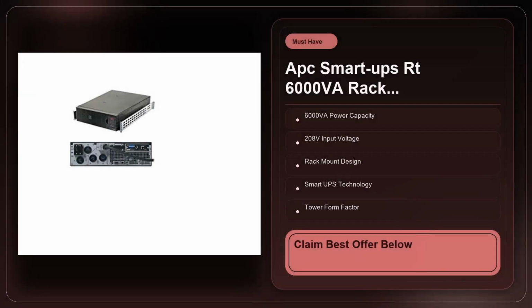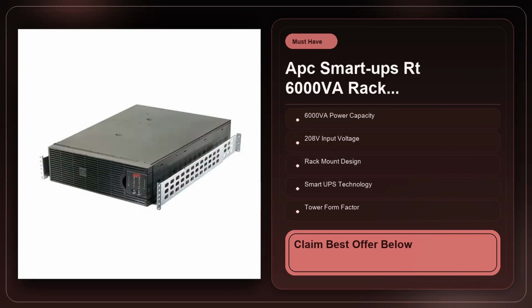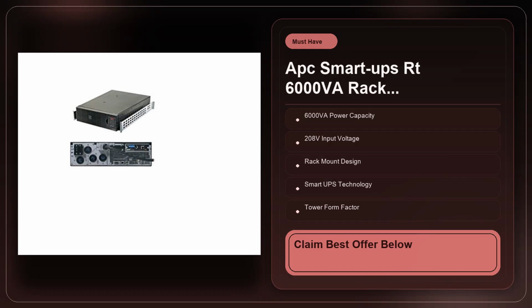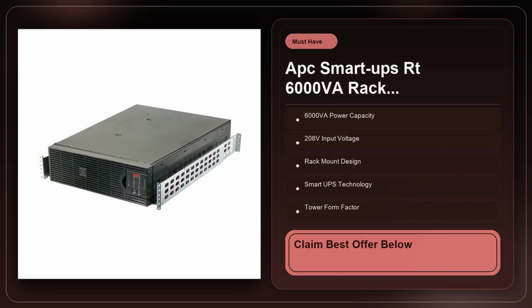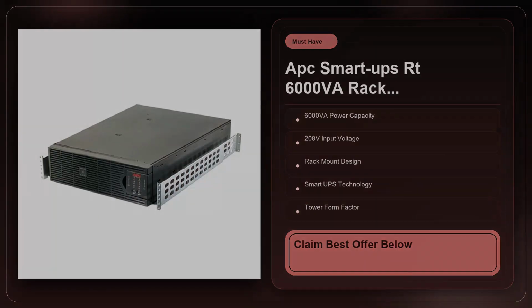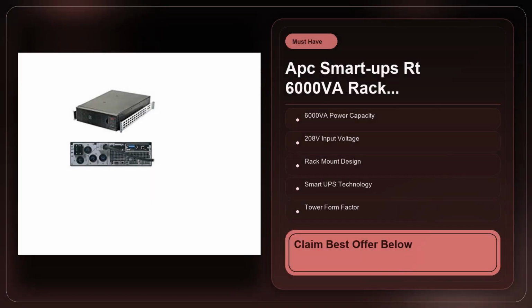Who should buy this? If you're running a server room that already uses 208V 3-phase power and you have a rack load between roughly 4 kilowatts and 5 kilowatts, this UPS fits nicely. Think of a typical 42U rack where you've got 4 blade servers, a high-density switch, and a backup storage system. The Smart UPS RT's 6000 VA rating translates to about 5.4 kilowatts of usable power, which is enough headroom to handle those loads plus a little extra for future expansion.